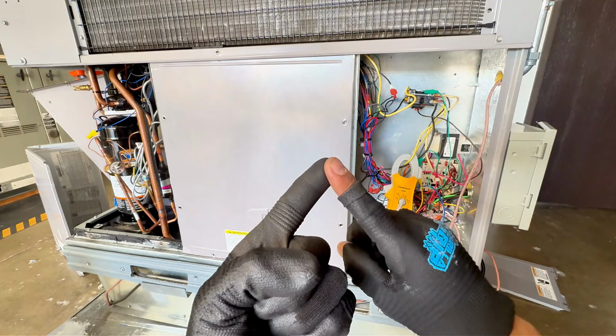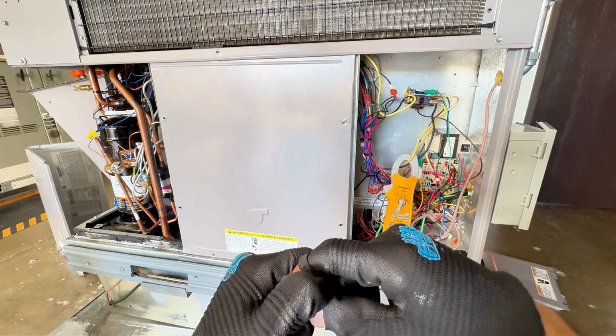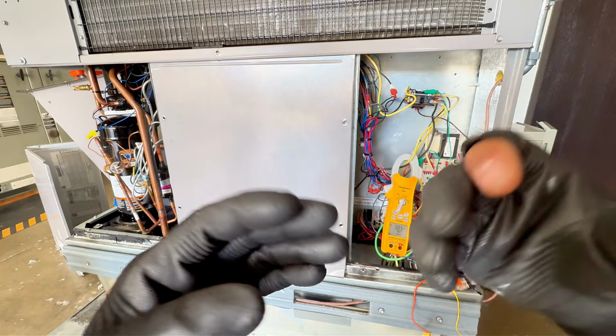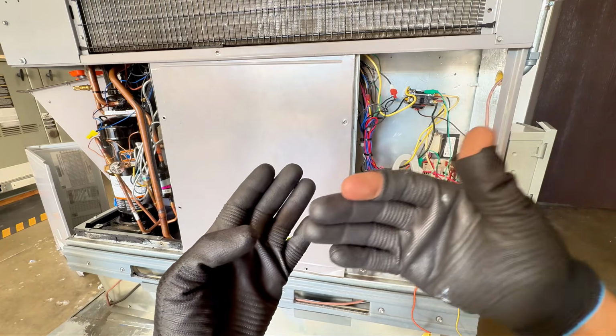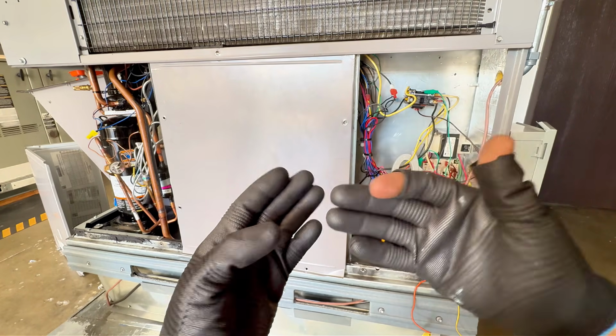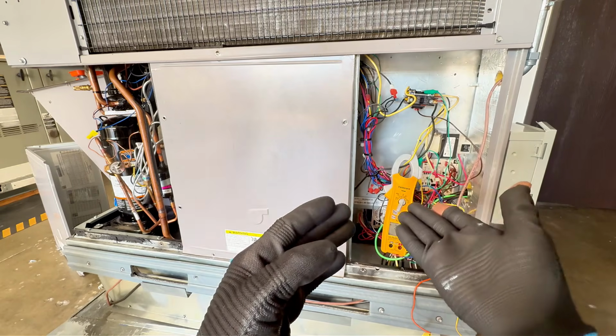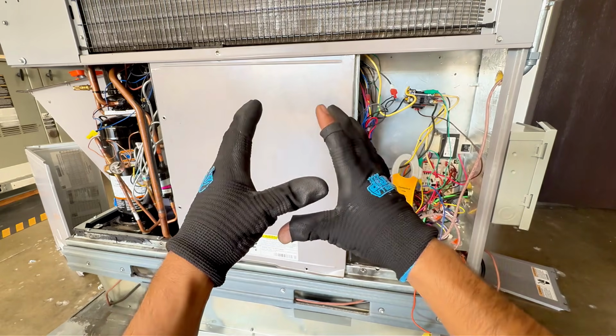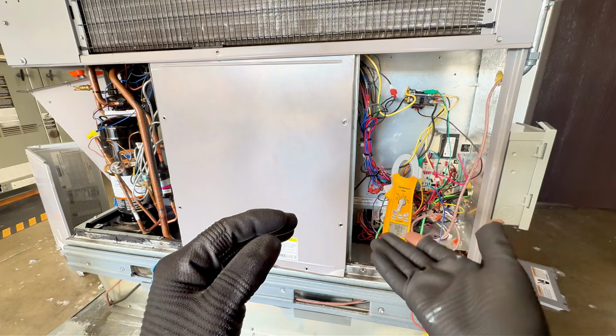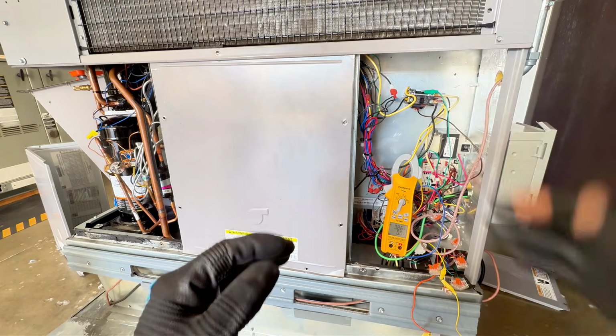So on a PSC, the amps go down with the restriction. With an ECM, if it's not a complete blockage, if it's just a restriction, just like a dirty filter or some closed supply vent or undersized return duct, with the restriction on an ECM, it's going to have your current go up.